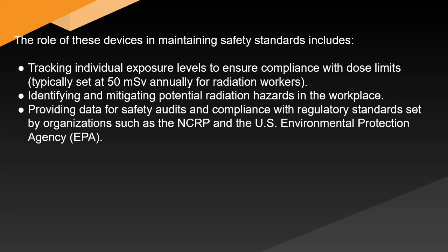The role of these devices in maintaining safety standards includes tracking individual exposure levels to ensure compliance with dose limits, typically set at 50 mSv annually for radiation workers, identifying and mitigating potential radiation hazards in the workplace, providing data for safety audits and compliance with regulatory standards set by organizations such as the NCRP and the U.S.